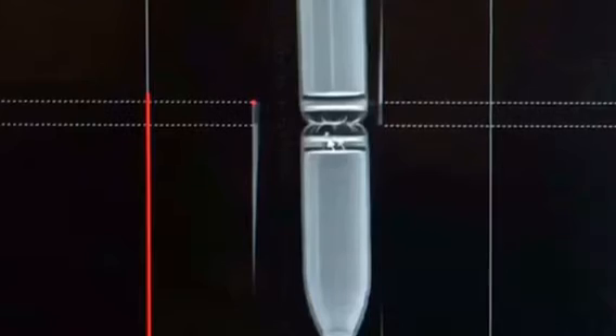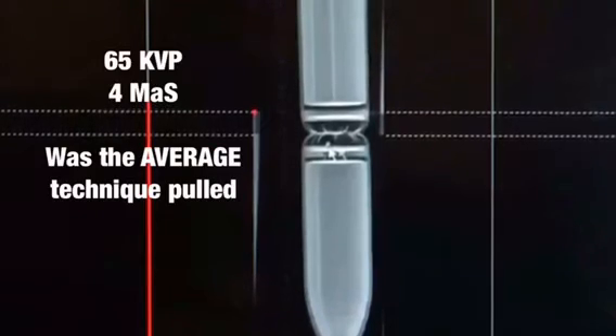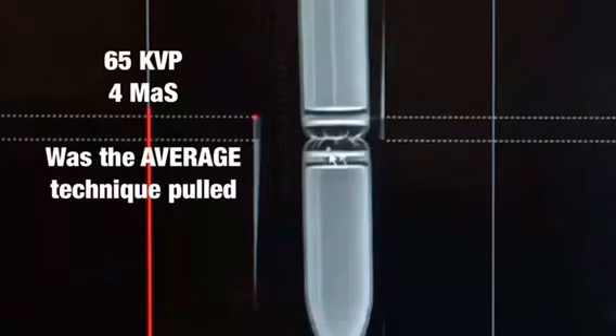The technical factors used for the particular exposure we made were 65 kVp and 4 mAs. AEC is not used for stitching exposures. This is because the tube and the bucky are constantly moving throughout the exposure, so there really isn't a specific cell that can be activated or properly used.